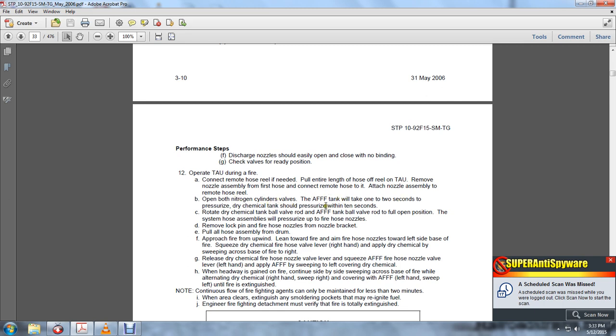Pressurized dry chemical should pressurize within 10 seconds. Rotate the dry chemical valve rod and the AFFF tank valve to the open position. System hose assemblies pressurize to the fire hose nozzle. Remove the lock pin from the fire hose nozzle bracket. Pull all of the hose assembly from the drum. Approach the fire from upwind. Lean toward the fire. Aim the fire hose nozzle toward the left side of the base of the fire.